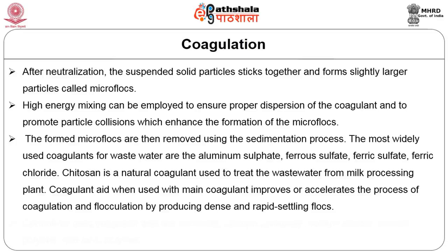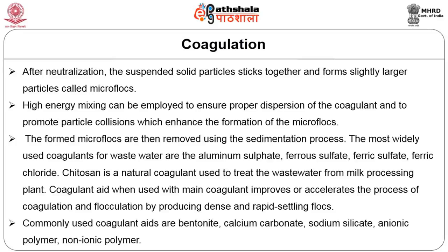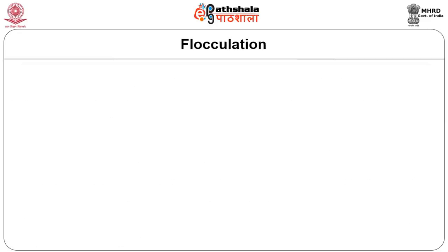The formed microflocs are removed using sedimentation. The most widely used coagulants for wastewater treatment are aluminum sulfate, ferrous sulfate, ferric sulfate, and ferric chloride. Chitosan is a natural coagulant used to treat wastewater from milk processing plants. Coagulant aids, when used with the main coagulant, improve or accelerate coagulation and flocculation by producing a dense and rapidly settling floc. Commonly used coagulant aids are bentonite, calcium carbonate, sodium silicate, anionic polymer, and non-ionic polymer.